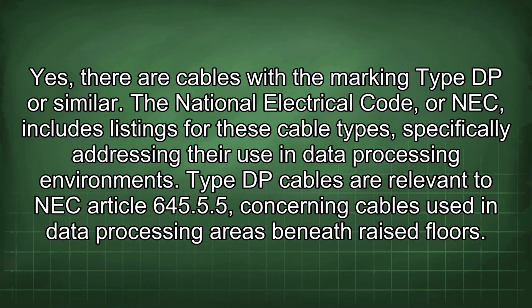Yes, there are cables with the marking type DP or similar. The National Electrical Code, or NEC, includes listings for these cable types, specifically addressing their use in data processing environments. Type DP cables are relevant to NEC Article 645.55 concerning cables used in data processing areas beneath raised floors.